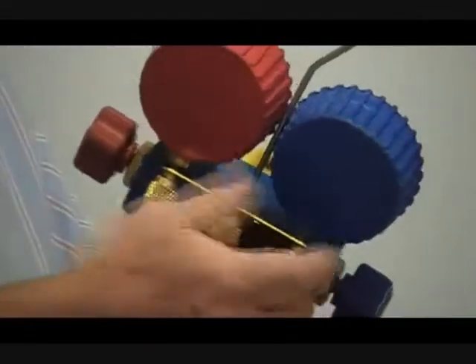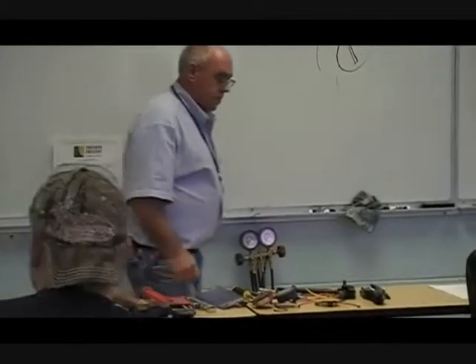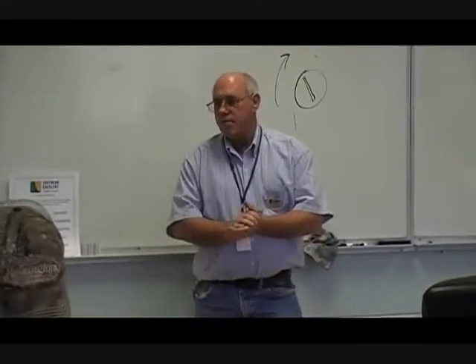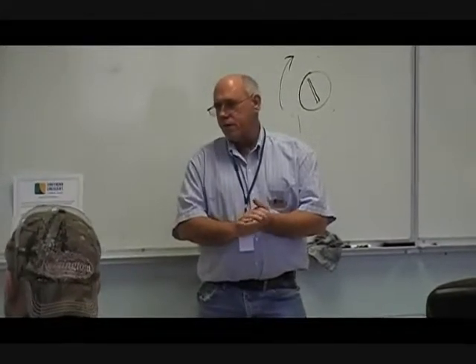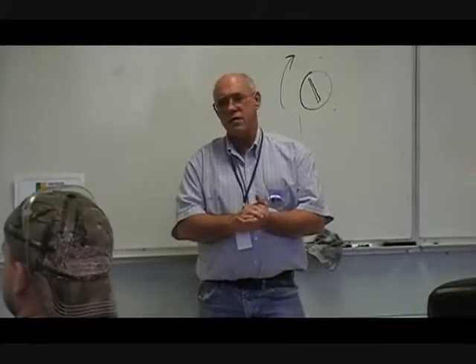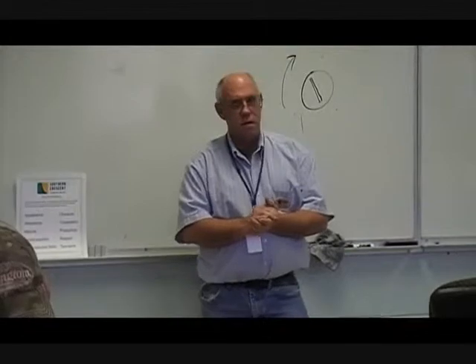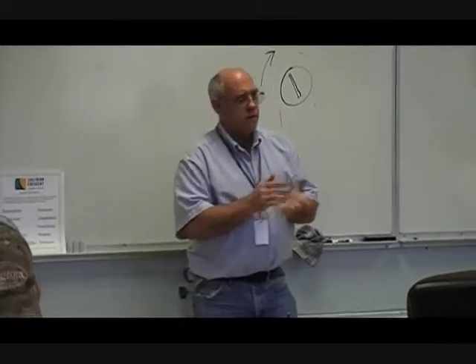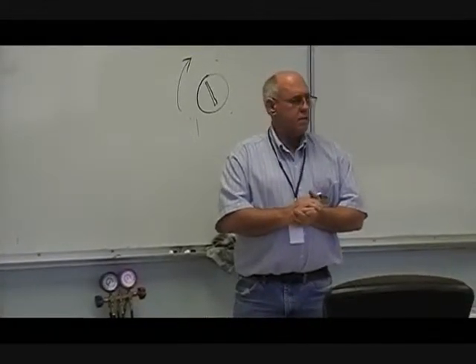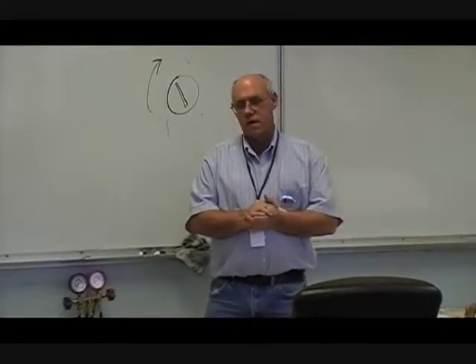Now, I have an extra hose in my hand, and I want you to compare what's on this hose compared to the other hoses. The reason being, we always talk about the gauges being rated, but we very seldom talk about the hoses. One of those hoses has a working pressure, I think it's 500 pounds, I believe. And the other one has a working pressure of 800 pounds. If you're dealing with 410A, you want to make sure that you have the hoses that are rated for the 410A, the higher pressure.